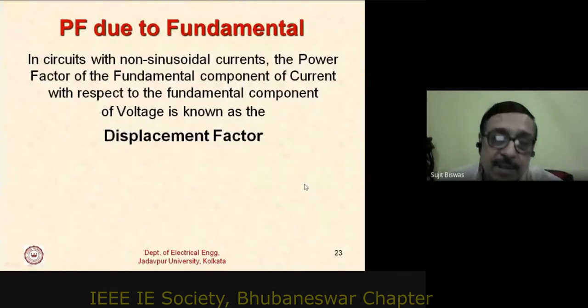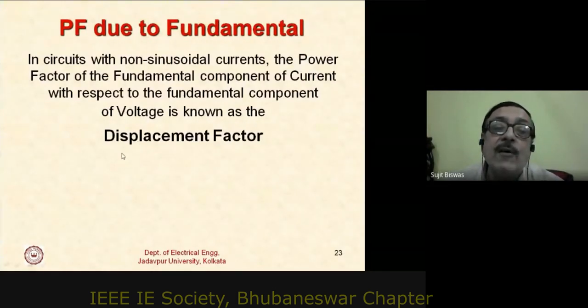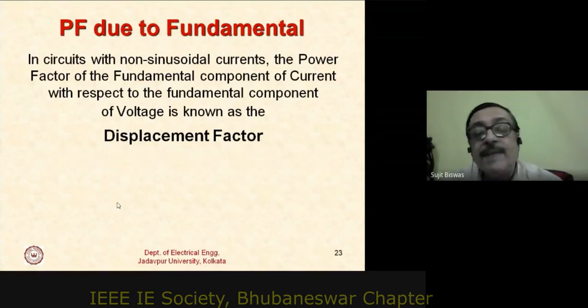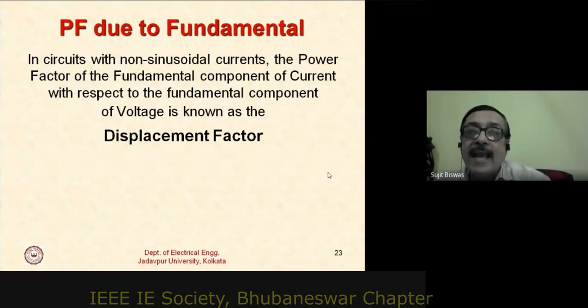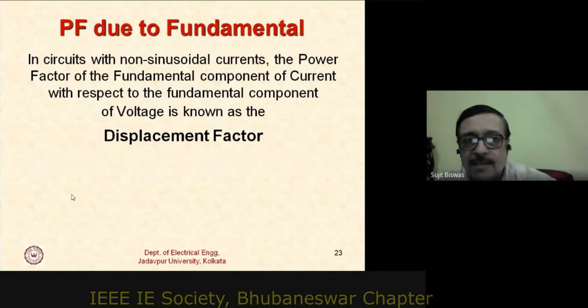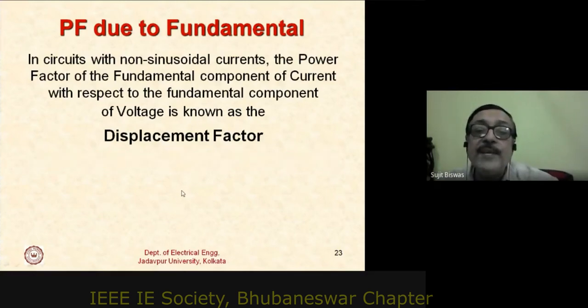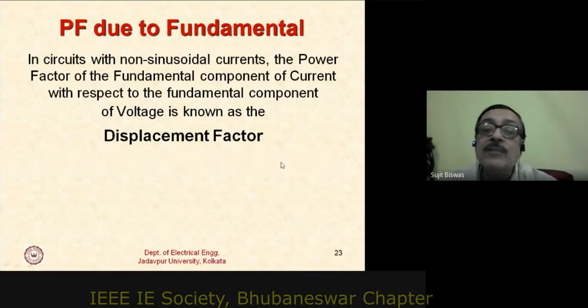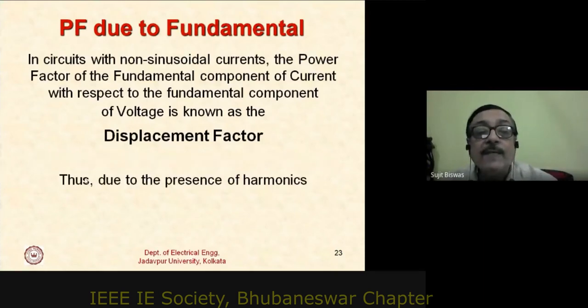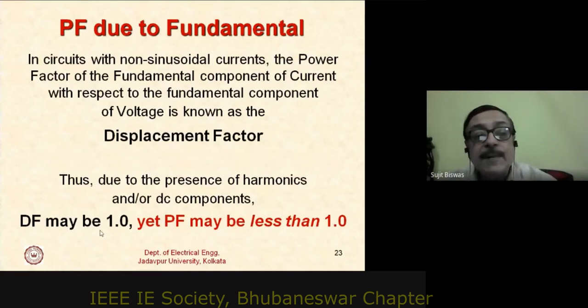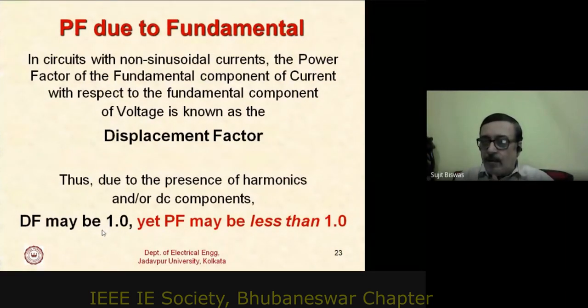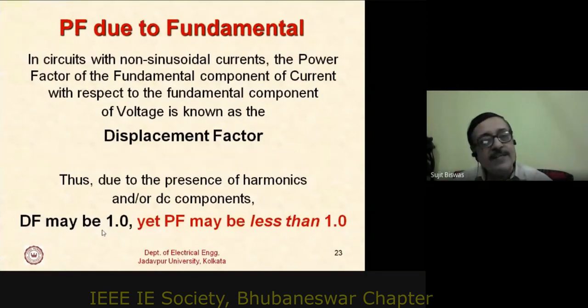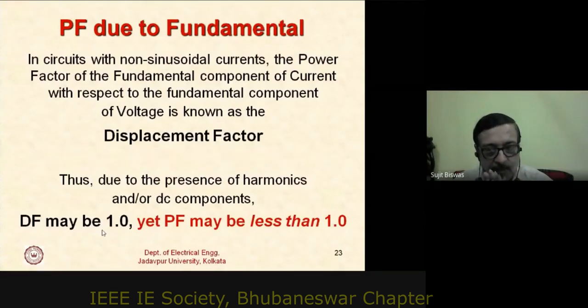To account for the fundamental component separately, displacement factor (DF) is defined as cos(θ₁), where θ₁ is the angle between the sinusoidal supply voltage and the fundamental current. In the presence of harmonics, the displacement factor may be unity yet the power factor may be less than one — meaning the fundamental current is in phase with voltage, but harmonics still reduce the overall power factor below unity. This is an important concept to appreciate.